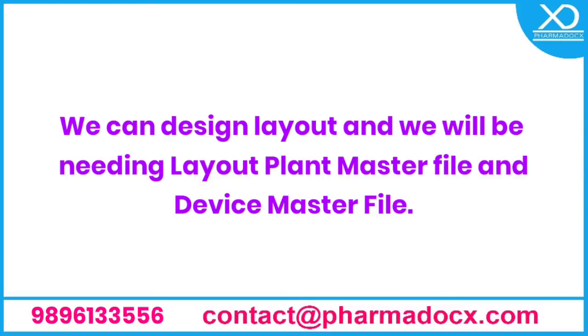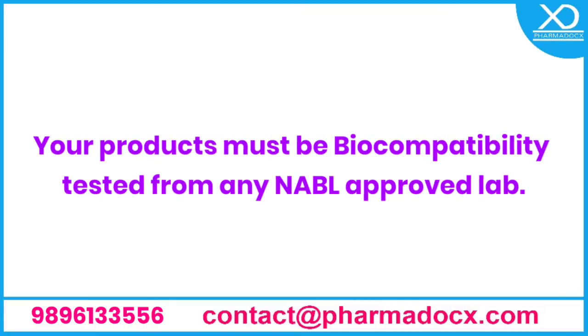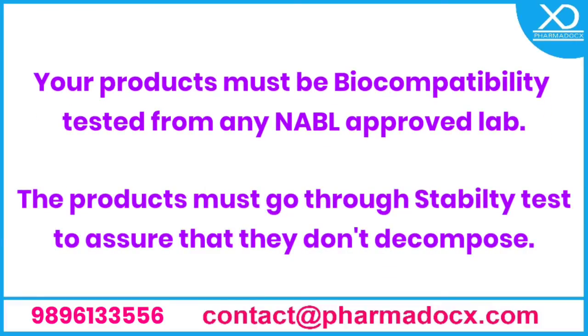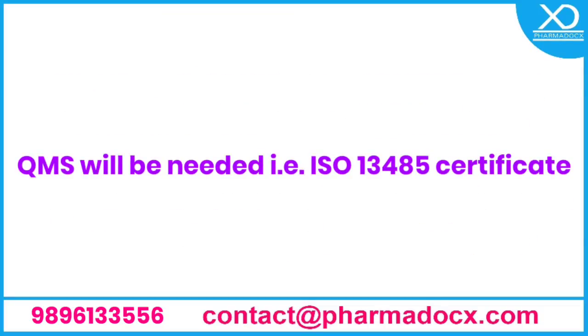Layout we can design. Then we'll be needing the plant master file, which also we ourselves can make. We can also make the device master file for your products. You need to get your products biocompatibility tested from any NABL approved lab. Also you have to do your product stability studies so that it is ensured that the shelf life of the product does not decompose. And we need your QMS, means your ISO 13485 certificate.